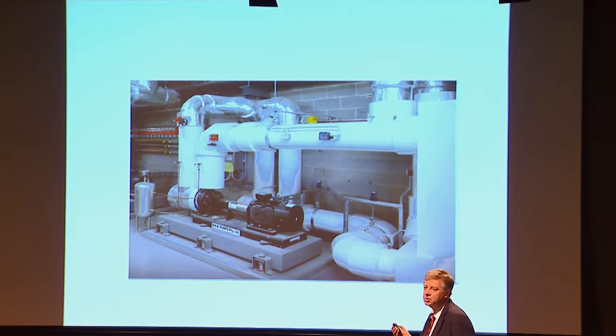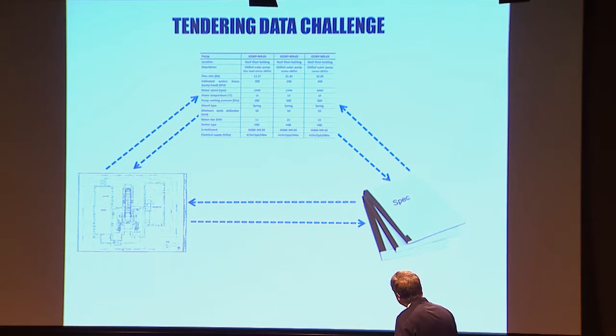So to get this pump installed, we've done a lot of research, we've looked at it end to end. It is around 120 parameters to get that installed. The first problem we typically get is that we might get about 4 or 5 parameters from a consultant, mainly the flow and a few bits and pieces. You'll find information scattered throughout the specification in different parts about the motors, the vibration isolation, all this sort of carry on. And then sometimes you even have to go and look at the drawings to work out whether it's an inline pump or an end suction pump. So that starts a whole chaotic process in terms of tendering.